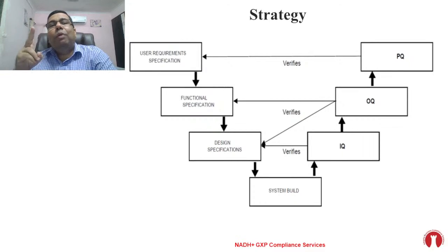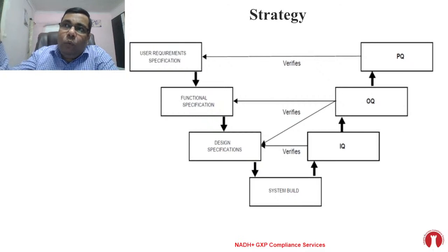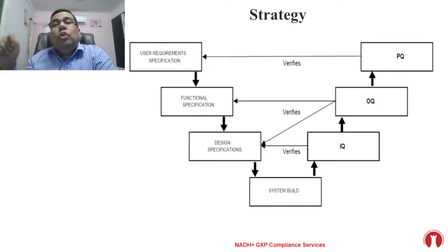Second, many people don't put this in the report, but I suggest including it: whenever you perform an IQ test, note why you are performing it—to fulfill a specific design specification requirement. You can write the reference number, such as the design specification reference number, maybe 1.2.4, or the functional specification number, so that you have traceability.